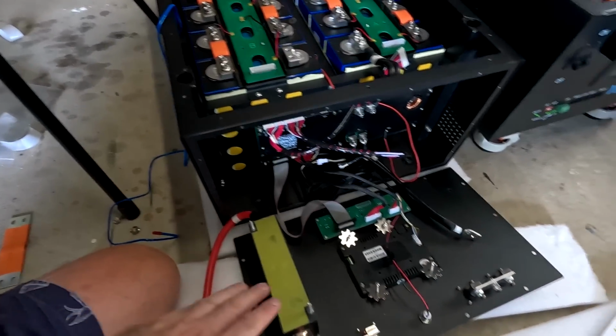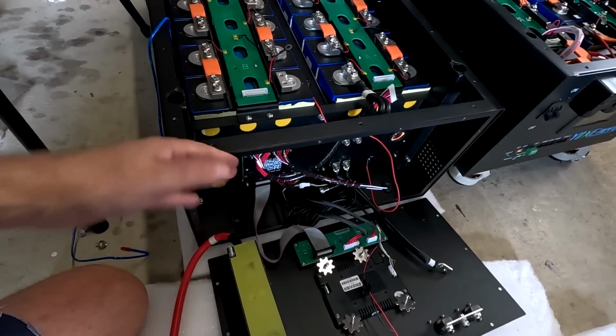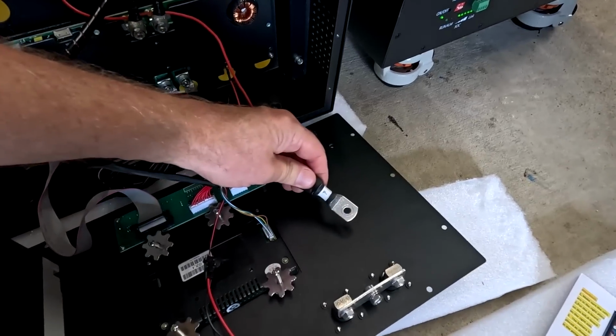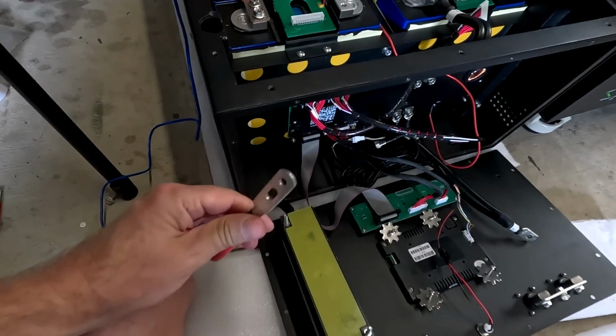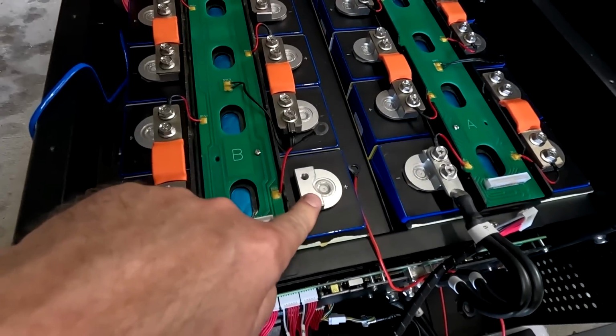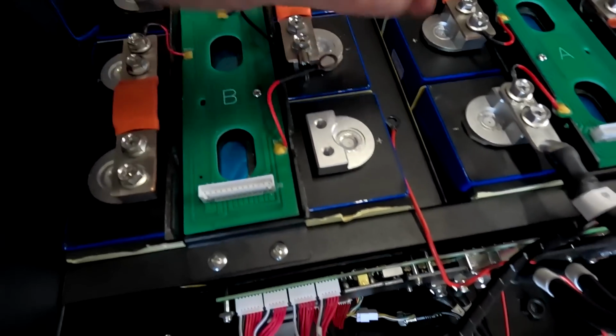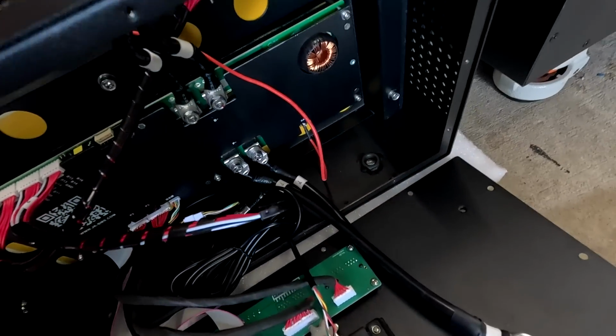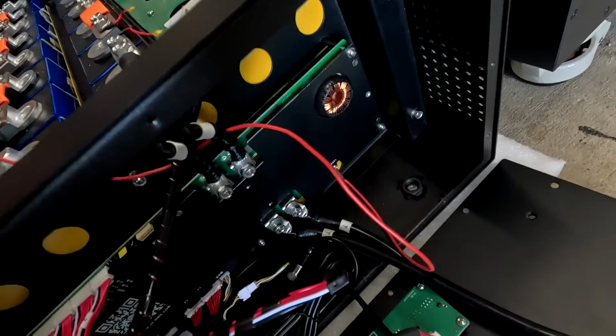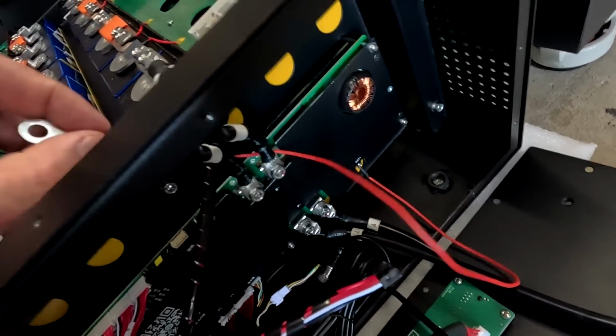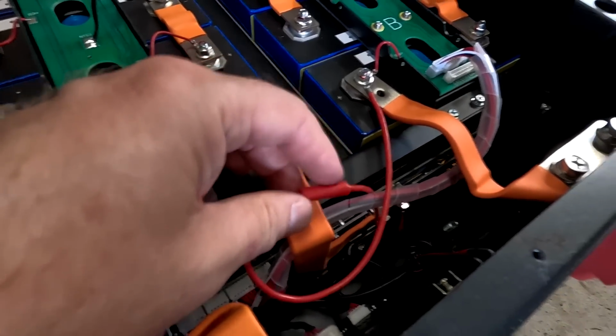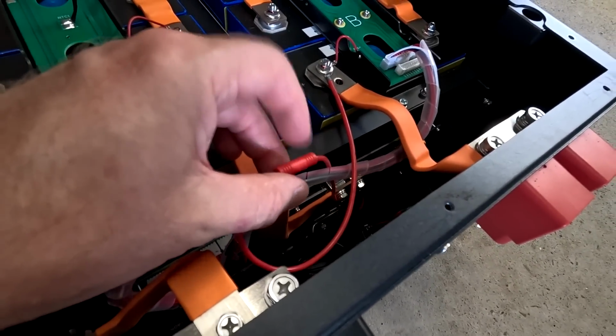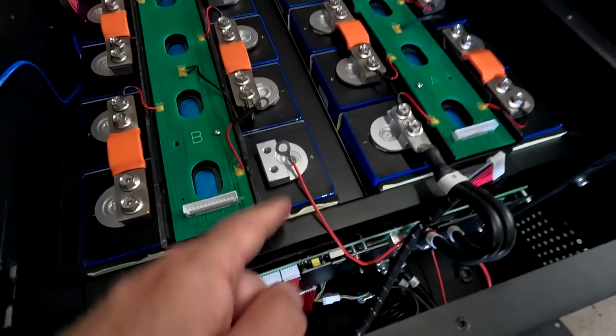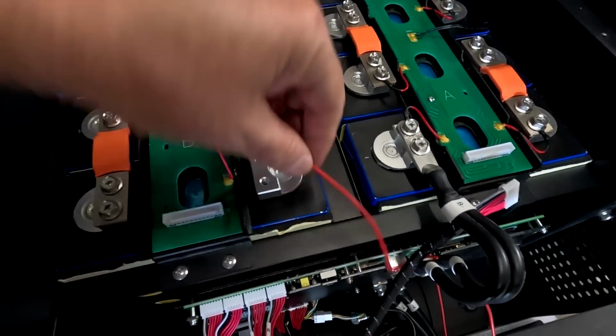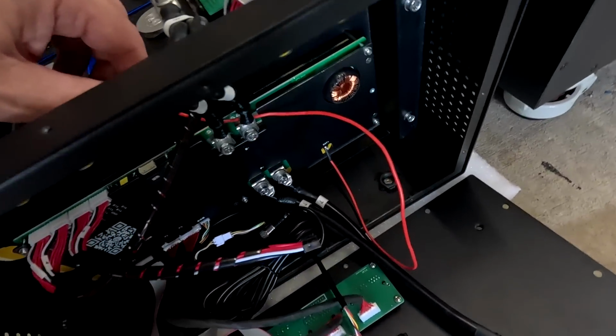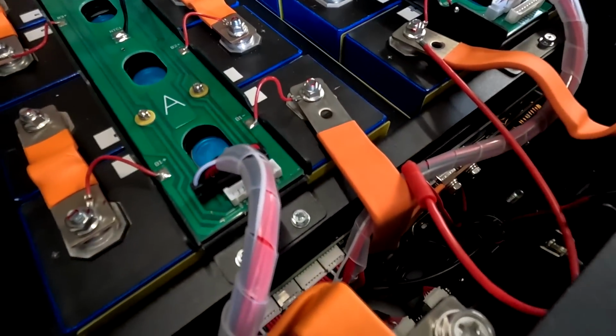Okay, and in the final step we can actually mount the front plate now back to the actual case, connect the P negative to our bus bar and the battery positive to the last terminal over here. Here connects the last balance cable as well as the positive for the BMS. And this one doesn't have a connector in between anymore, it's just a piece of wire now. Here you can see it here, this one has a connector. So if you want to disconnect the BMS, you just disconnect the cable, the positive here, and the BMS is dead. You can't do this here, you have to actually unscrew this cable. Okay, that's another change. Maybe this cable is cheaper than the one with the connector.